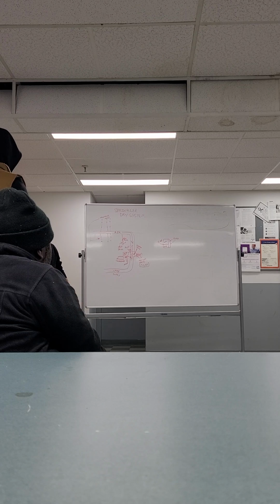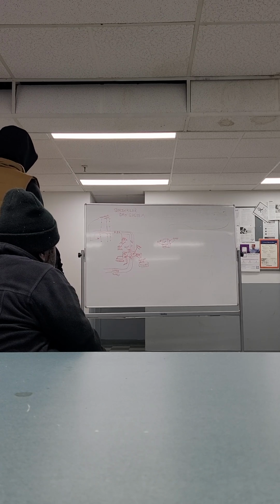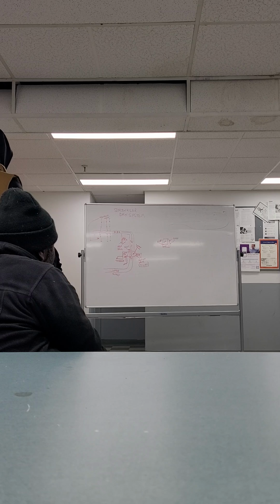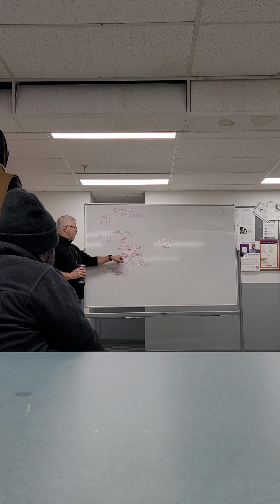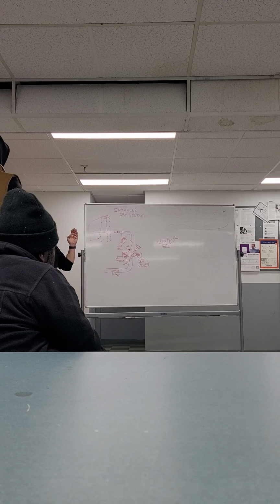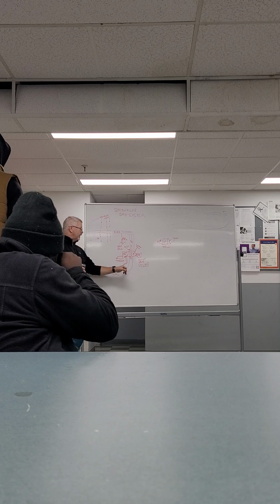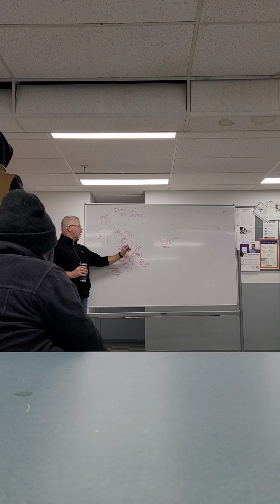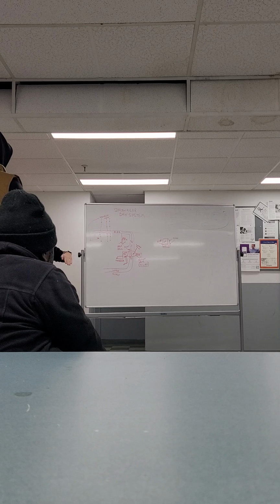I don't know who it is, we've had so many contractors fixing these things, but all the broken parts are inside of the closets, so we can take a look at them and see what happens. Now, I completely understand what you're saying. That's your basic thing. We have a compressor on each level that keeps a constant 50 pounds on that to prevent that flapper from going up. And then you have about probably 40, 45 pounds of water there. If that flapper goes bad, the water rushes in and you're done.